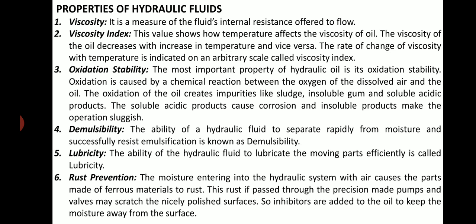Properties of hydraulic fluids. Viscosity: It is a measure of the fluid's internal resistance offered to flow. Viscosity Index: This value shows how temperature affects the viscosity of oil. The viscosity of the oil decreases with increase in temperature and vice versa. The rate of change of viscosity with temperature is indicated on an arbitrary scale called the viscosity index.